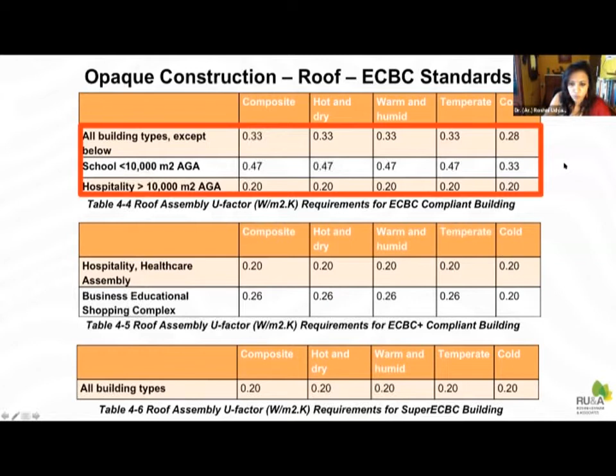As per the standards, we have 0.3, which is very stringent. A 150 mm RCC slab will have a U value of close to 3.7. So to achieve 0.33 means your roof is super energy efficient—that's the basic standard. The roof allows a lot of heat to come inside the building, so stopping that heat flow makes the building efficient.